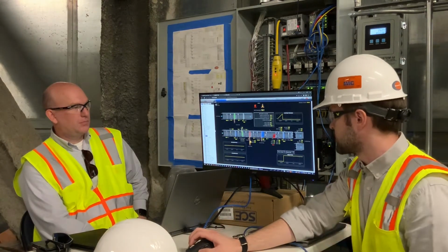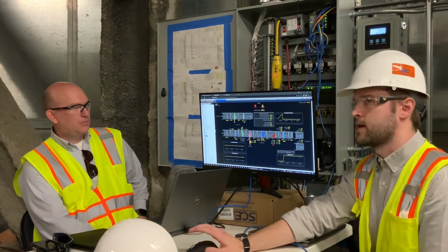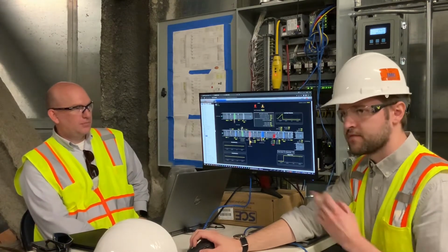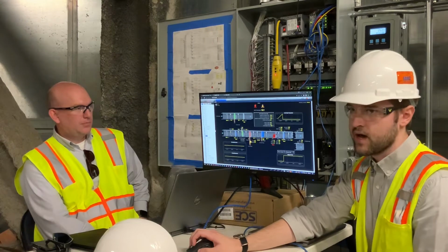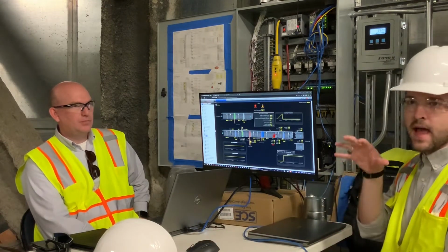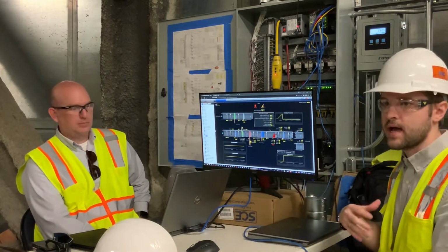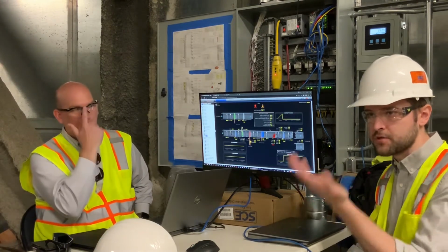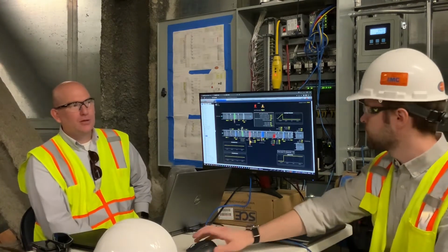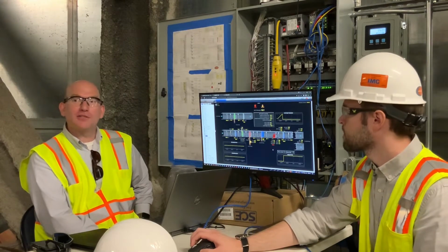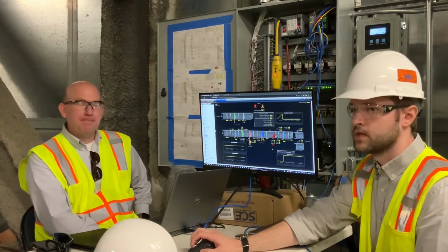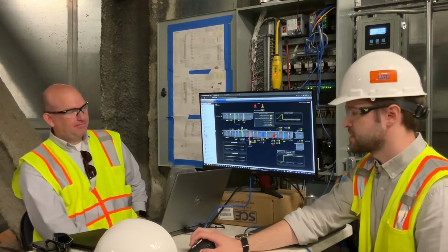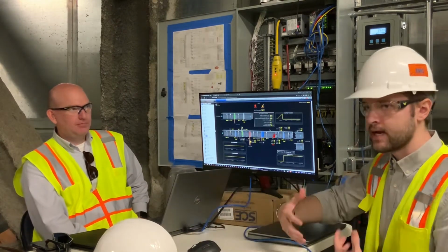The other key difference between this unit and air handlers 1 through 4: you have a preheat valve and a cooling valve, that's the same, but you do not have a reheat valve. All reheat is done at the labs themselves. Every lab, all the supply boxes will have reheat coils in them to bring the temperature back up to what's appropriate for the lab. There are some VAVs, but the majority of it's Phoenix. They're pressure independent. Yep. So we'll talk about the Phoenix stuff. It's a separate system that we're pulling data from.